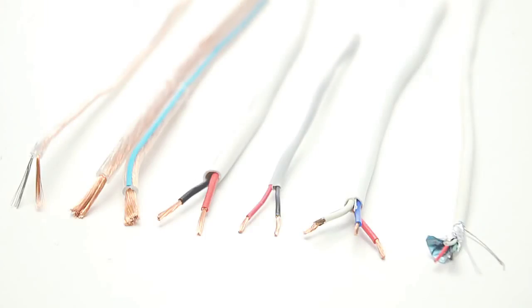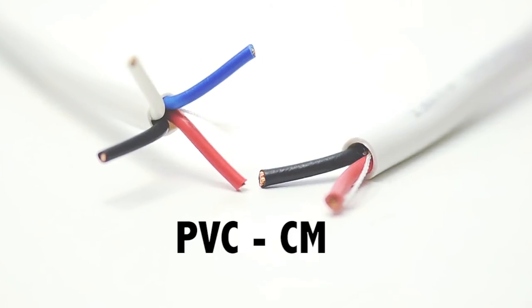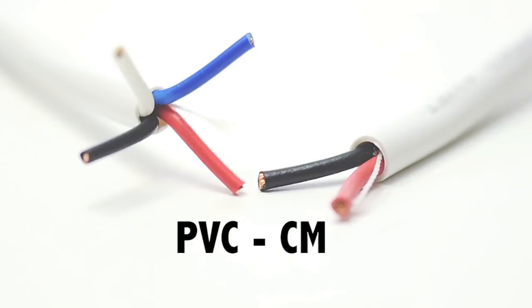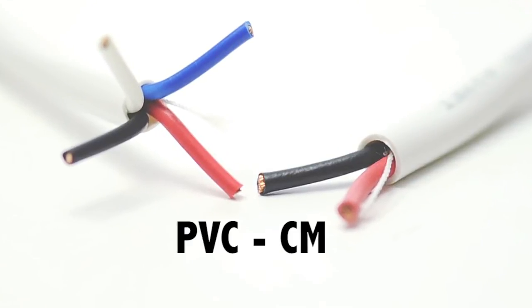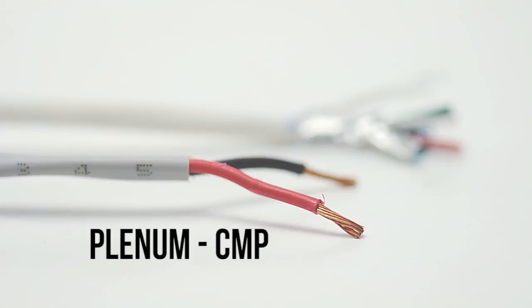Speaker wire jackets have different ratings based on where the cable will be run. There are several classes of jacket ratings, but ShowMeCables simplifies speaker wire to either PVC or plenum rated. PVC is technically a CM rated jacket which can be used for general purpose activities including in-wall installations. Plenum cable, specified as CMP, is used for advanced installations and plenum air return spaces.